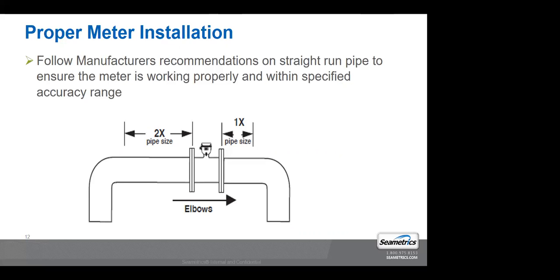When you look at mechanical meters, like your propeller style flow meters, a basic propeller meter would require 10 pipe diameters upstream. So on a 10-inch pipe, you need 100 inches upstream and 5 diameters downstream, so 50 inches on the downstream side. Now there are straightening vanes, wafer cones, different types of things you can put in front of those propeller meters to shrink that straight run requirement. It typically reduces it to half on the upstream, and I don't think it reduces it on the downstream. I think instead of 10 on the upstream, it's 5, but you still need the 5 on the downstream.